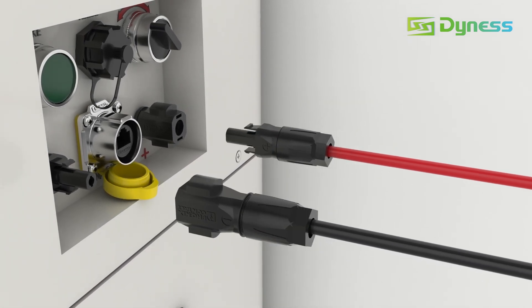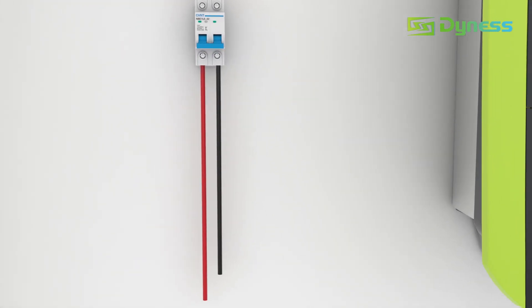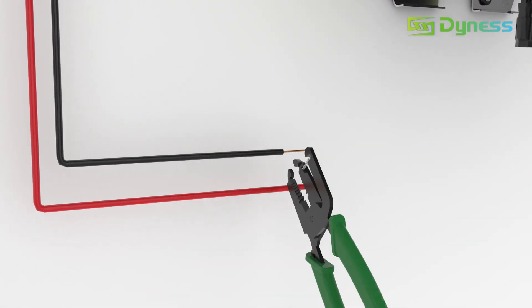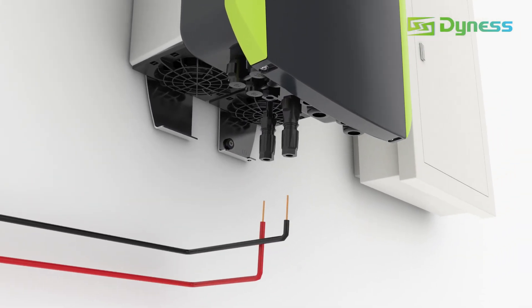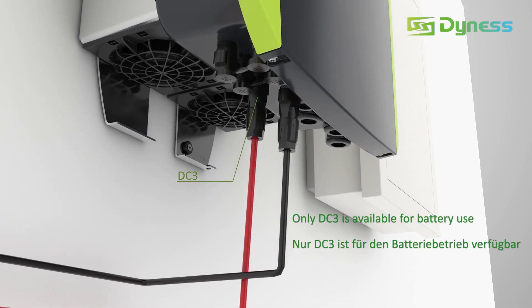Lock the connectors into the BDU. It is strongly recommended to install a DC breaker between the inverter and battery for electrical protection. Make cable termination, lock the battery side, and lock the connectors into the DC3 port.